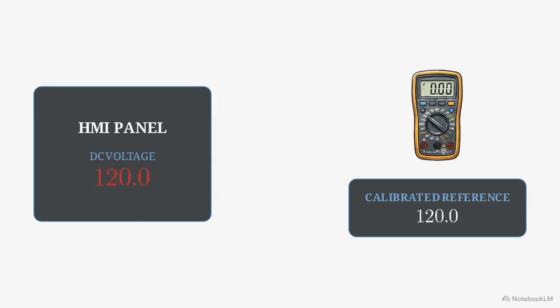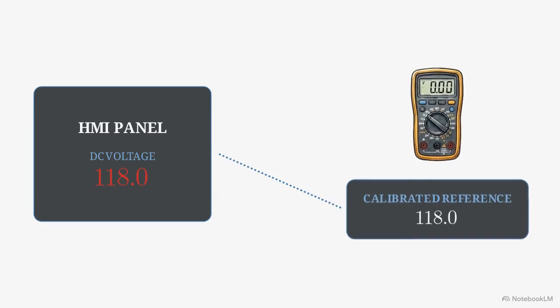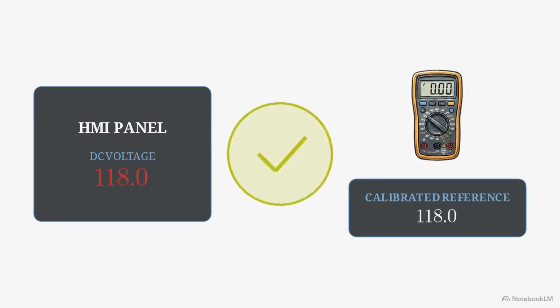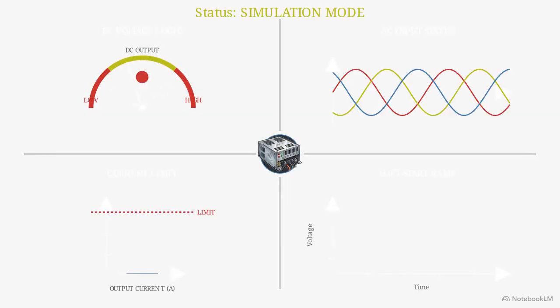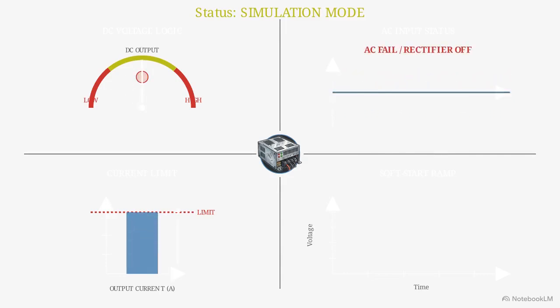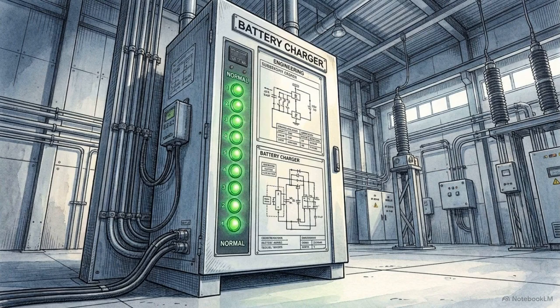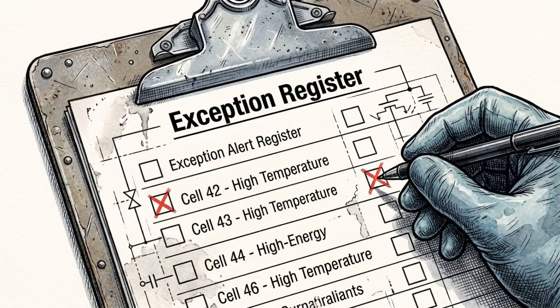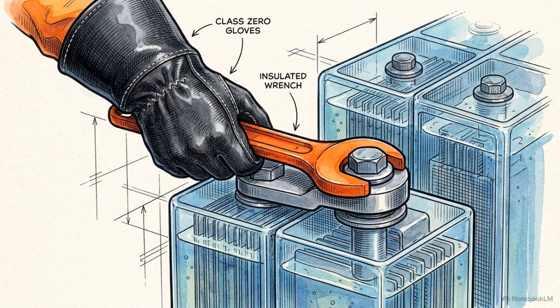As these faults are safely simulated, a correlation check is performed. The values displayed on the charger's internal screen are cross-referenced against independent readings from calibrated multimeters to ensure the onboard computer is reporting accurate data. The remaining functional logic checks simulate high and low DC voltages, AC input failures, current limit triggers, and the system's soft start behavior. These logic tests confirm that the charger's internal systems will accurately report and react to any real-world electrical anomaly. If any discrepancies appear on the interface, or if chemical anomalies were found before the discharge test, they must be recorded in the exception register and physically resolved before the system can be signed off.